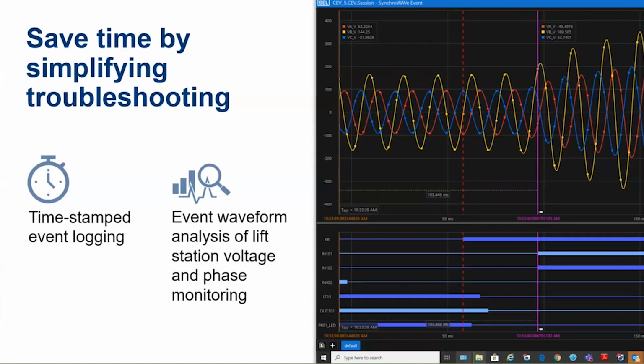So if you ever wonder if you're getting great power and if any fluctuation of voltage or voltage transients are causing you issues at the station, adding this phase monitor card is about a $200 cost adder to the product. And it'll do your phase monitoring for you as well. There's several different things that you can do when you're setting this up, but it automatically detects whether you have open delta or a Y connection to your power source, which is really nice.